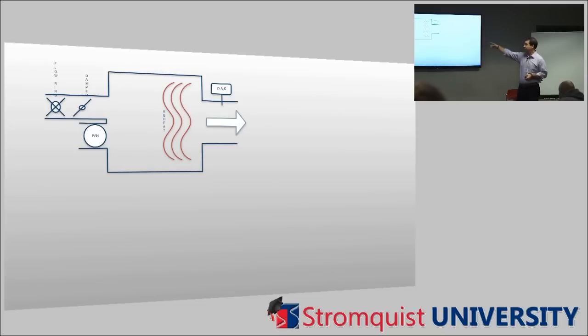And then they actually even have a spot for reheat, so when they call for heat, you'll see different types of reheat, but this will be electric reheat. Essentially you've got a little heat strip in there that heats up, and that 55 degree air turns into whatever it needs to be if they need to be heated up in that space. Okay, there's a whole, I think it's 2-day class on VAV boxes, so that's your intro level in 35 seconds. But it's a great class that we teach here if you guys ever need to know more about VAV boxes.